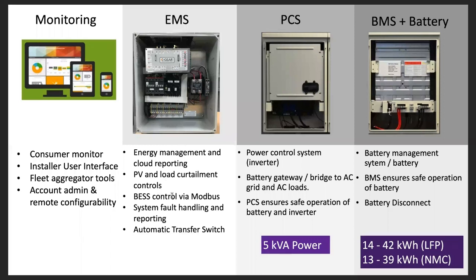There's also battery control via Modbus serial connection. It also handles system fault handling and reporting. And again, it houses the automatic transfer switch circuit as well. As far as the battery system itself is concerned, it consists of two basic systems. One is components or subsystems within the battery. One is the PCS, the power control system, which is basically the inverter and the power electronics, transformers, stuff like that. The PCS acts as a battery gateway or a bridge to AC grid and AC loads, and it ensures a safe operation of the battery and inverter.